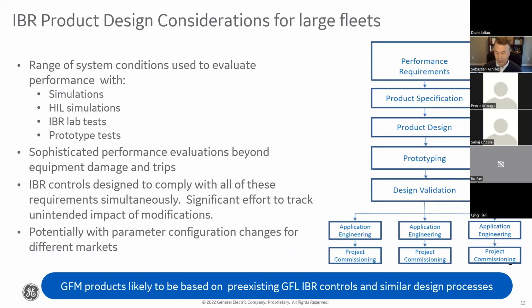That's maybe obvious, but when you're verifying compliance to all these requirements, it's relatively common that you'd do a modification in the product to meet a particular requirement where you have trouble, and by doing that, you solve the problem you're trying to address but create a different problem with something else. So you have to continuously verify that you're not having unintended consequences from the changes you perform.